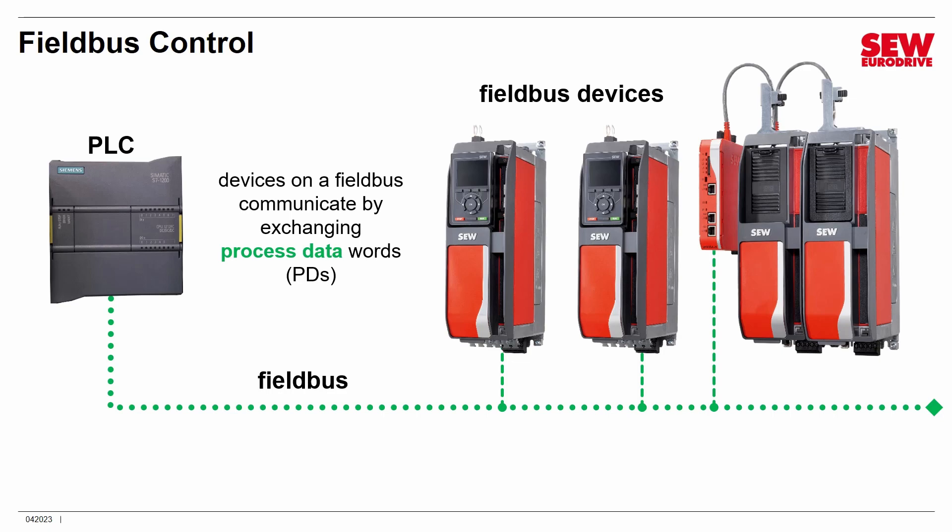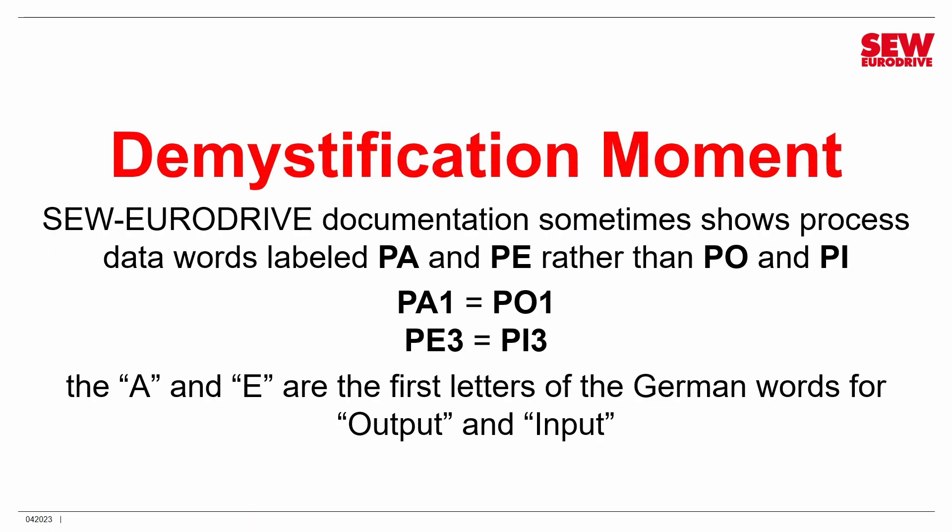Process output words typically carry commands and parameters telling VFDs what to do, while process input words contain status information going back to the PLC. One clarification: in some SEW documentation and software, POs and PIs may be labeled PA and PE. That's German — A and E are the first letters of Ausgang and Eingang, meaning output and input. Just mentally substitute PO and PI and you'll be fine.